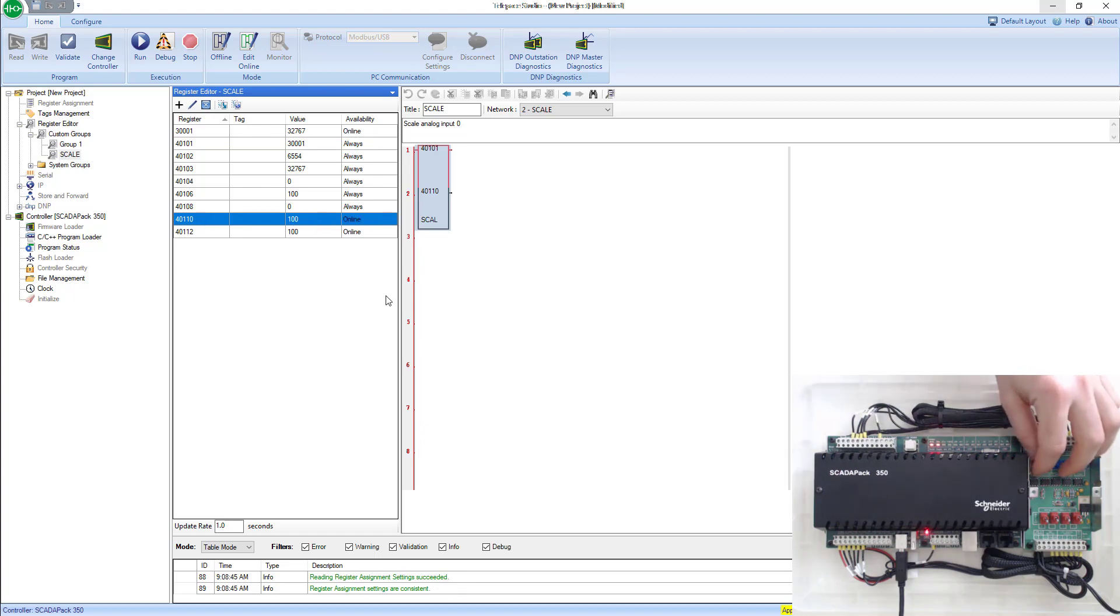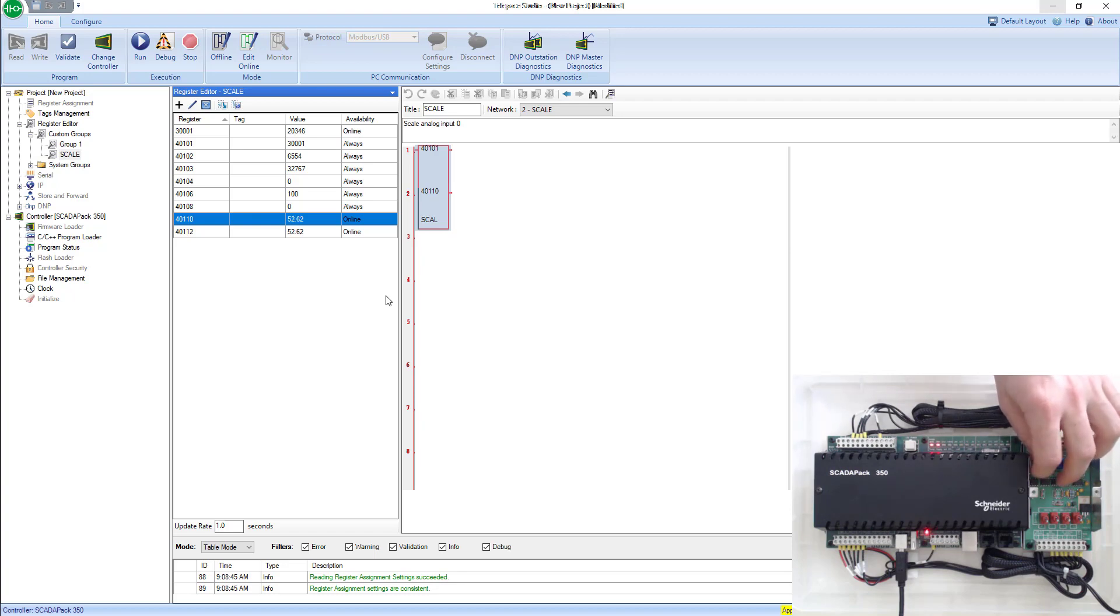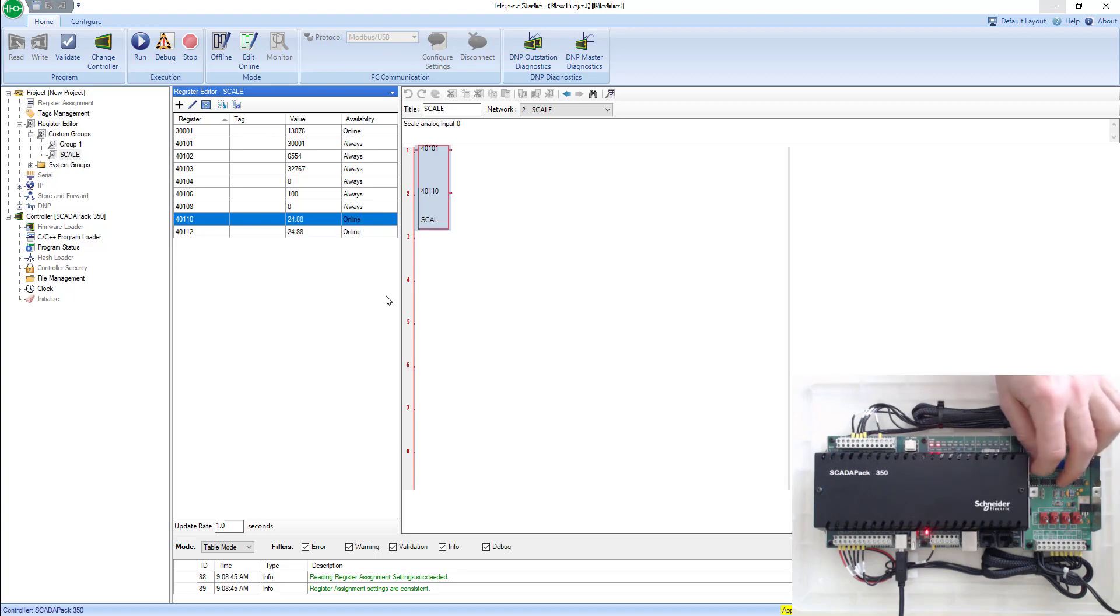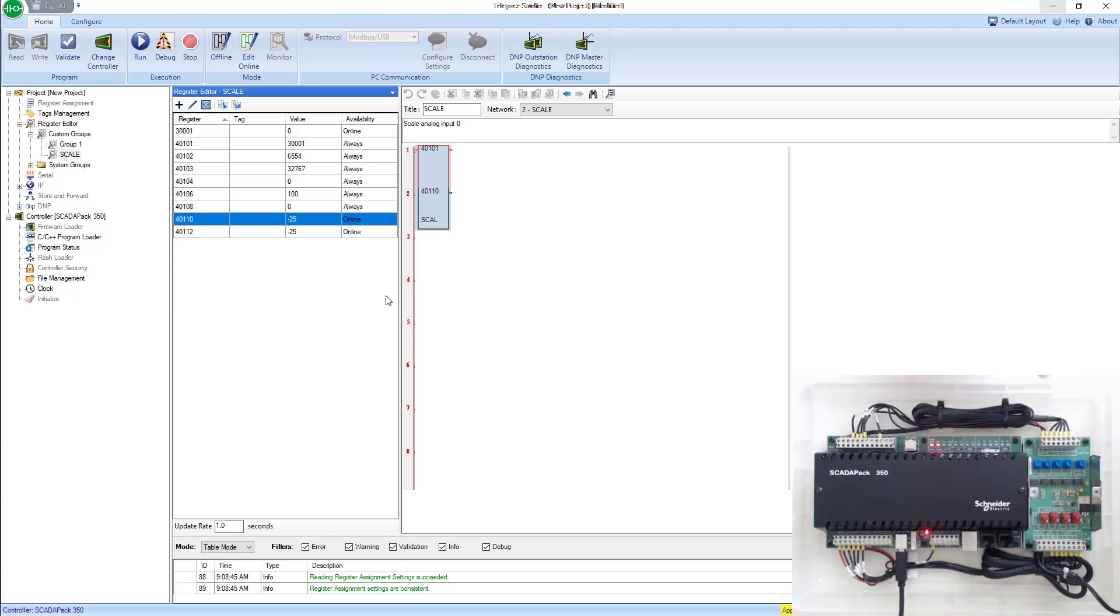If I scale it down to about 6554, I'll notice this will be about zero. It would be pretty much impossible to get it right on 6554, but you get the gist of it. And then if I go all the way down, wrong direction, all the way down, it's negative 25. So that's how you scale an analog input in telepace.